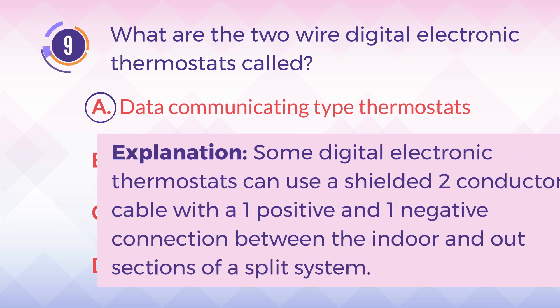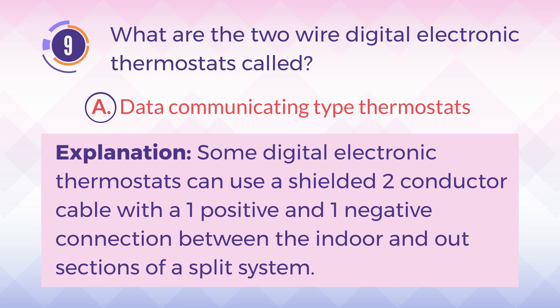The answer is A. Data communicating type thermostats. Explanation: Some digital electronic thermostats can use a shielded two-conductor cable with one positive and one negative connection between the indoor and outdoor sections of a split system.